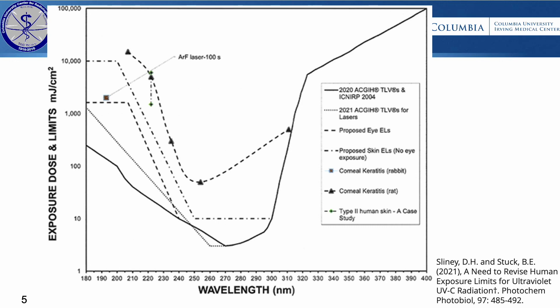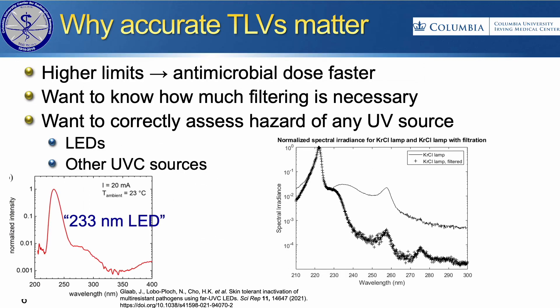With the help of many of these studies that have used a few wavelengths throughout the UVC, the ACGIH recently updated their TLV recommendations. They actually split the eye exposure limit and the skin exposure limit, and really increased the dose that is allowed in an eight-hour period for wavelengths less than about 240 nanometers.